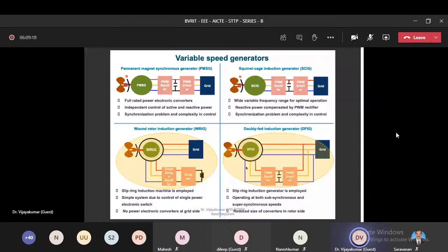Subsynchronous means, for a 4-pole machine at 50 Hz frequency, 1500 RPM is the synchronous speed. So in this system, below 1400 RPM also, you can operate as a generator, up to 1600 RPM super synchronous speed, that is above synchronous speed. So synchronous speed is 1500 RPM. Below it by 100 RPM you are operating as a generator, and above it by 100 RPM you are operating as a generator.